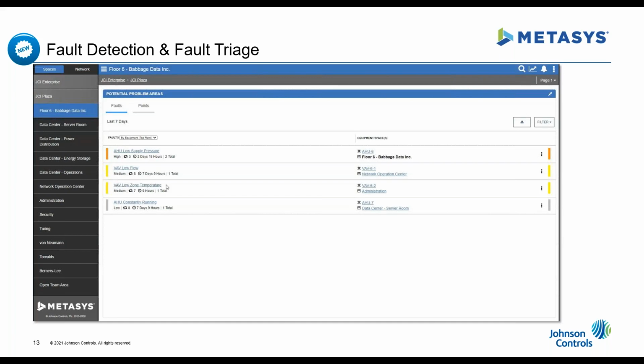Take an air handler, for example. Perhaps it's pushing out air that's too cold because a cooling valve is stuck open. We certainly want to know about that condition, but today we'd probably just set up an alarm on it. There are plenty of reasons an air handler might push out colder air for a short period, so you end up with a nuisance alarm.